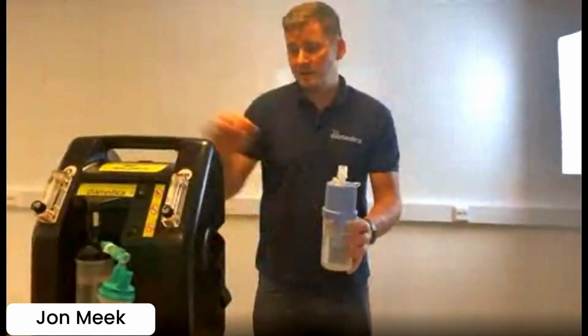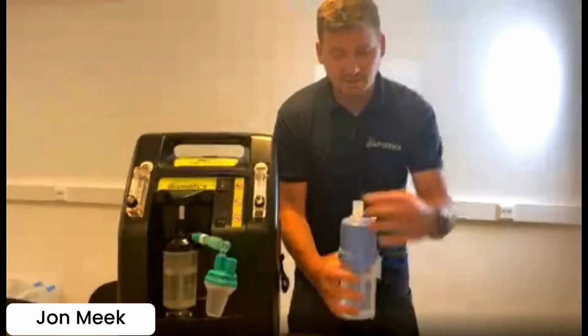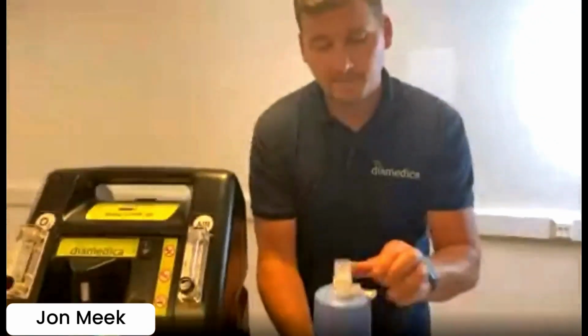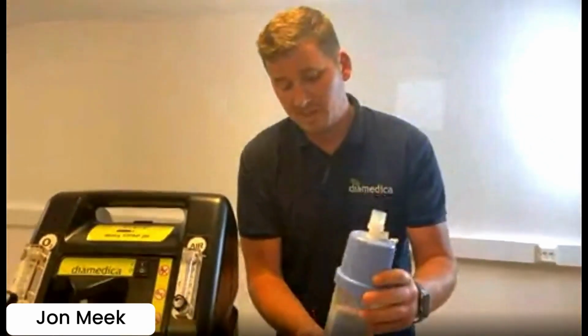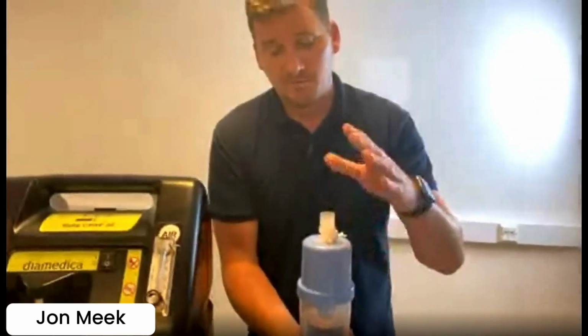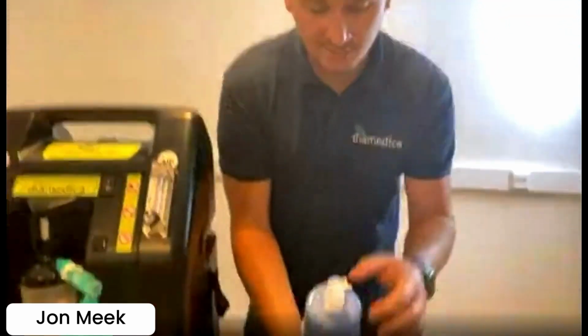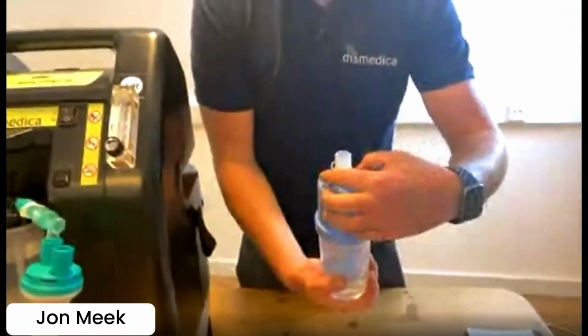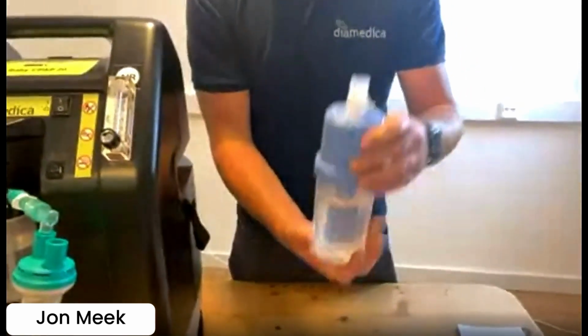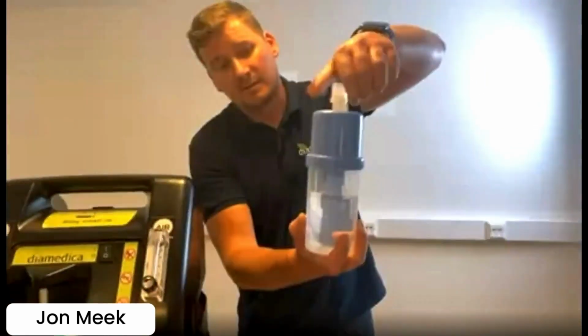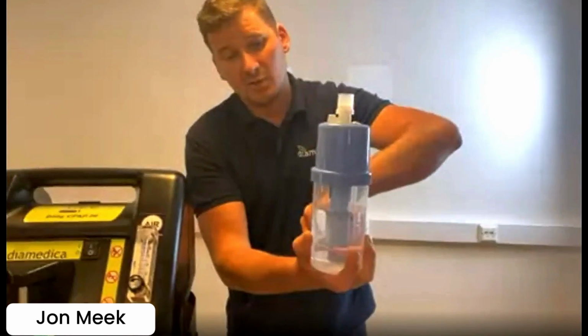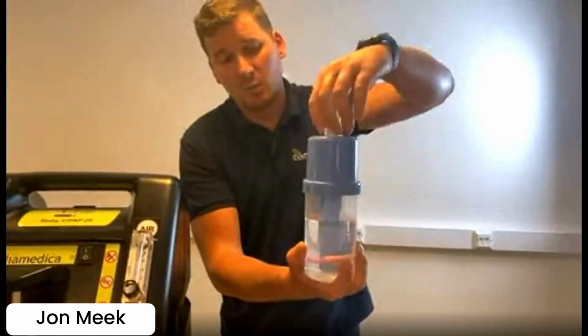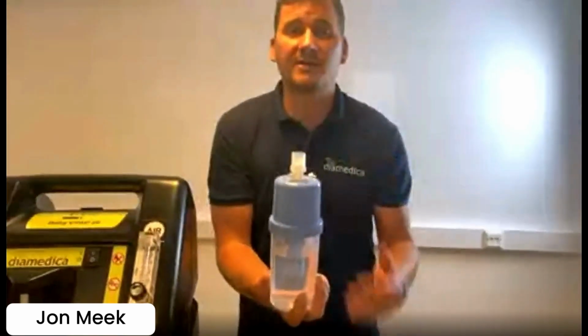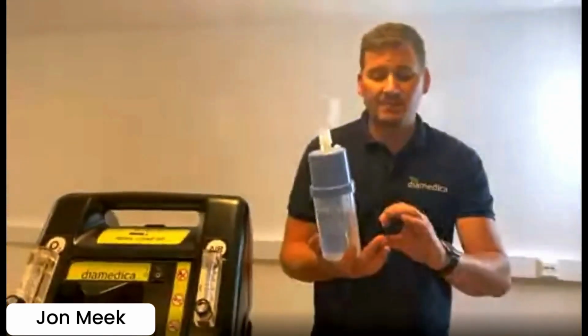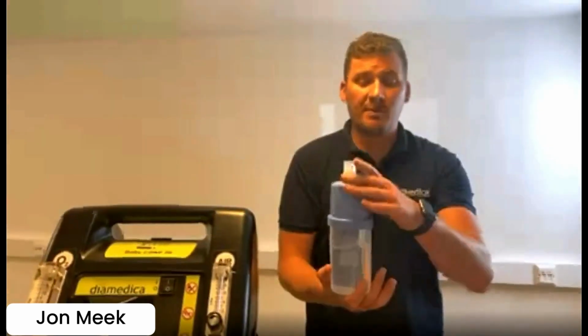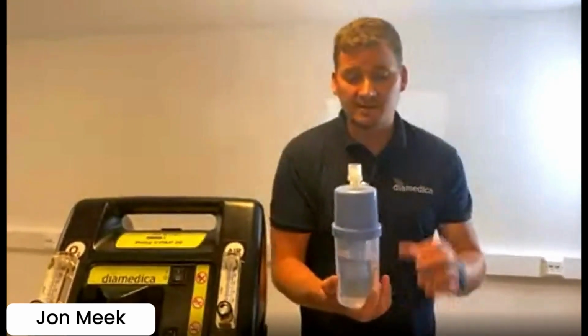So on the other side, which I'll show you in a second, this is what generates the pressure. This is a bubble bottle. This bubble bottle provides safe bubble CPAP at an accurate pressure and flow to the patient. What we have on here is a simple dial from 0 to 10. The higher you go, the deeper it goes, and the deeper it goes, the more pressure you have to create to generate bubbles. This is why it's called a bubble CPAP. So if it doesn't bubble, you're not providing that pressure of CPAP. And I'll show you that in a second.